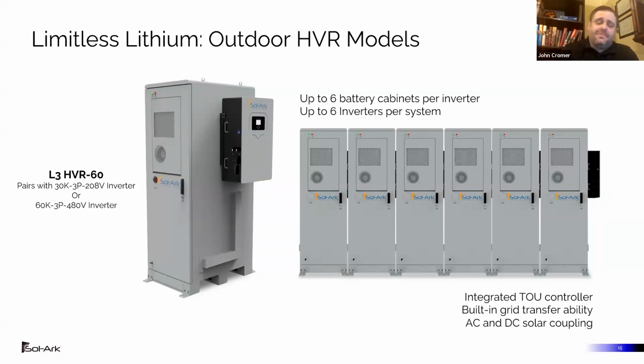Our indoor solution can go up to 10 inverters and can go up to 16 battery cabinets per inverter. And that's like a 10 megawatt hour battery. I've yet to see a 10 megawatt hour battery. There are multi-megawatt hour batteries out there with Sol-Ark batteries. I've yet to see one fully exhaust the capability of the system for our indoor unit. Our outdoor unit, we constrain a little bit more to up to 6 inverters and up to 6 battery cabinets per inverter. And a lot of that has to do with the internals of the cabinet itself.